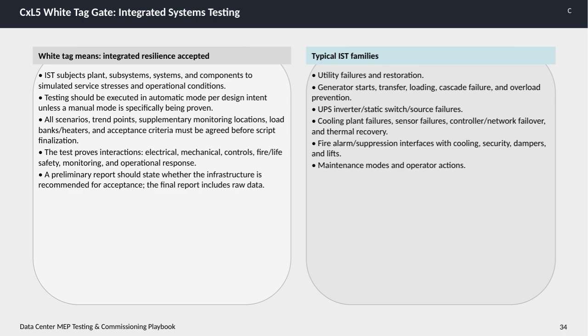After testing, a preliminary report indicates whether the infrastructure is recommended for acceptance, while the final report provides all raw data for detailed review. Typical test scenarios include simulating utility failures and restoration processes, managing generator operations, including startup, transfer, and overload prevention, testing uninterruptible power supply failures, assessing cooling plant issues and sensor or controller failovers, as well as verifying fire alarm and suppression interactions with cooling, security, dampers, and elevators.